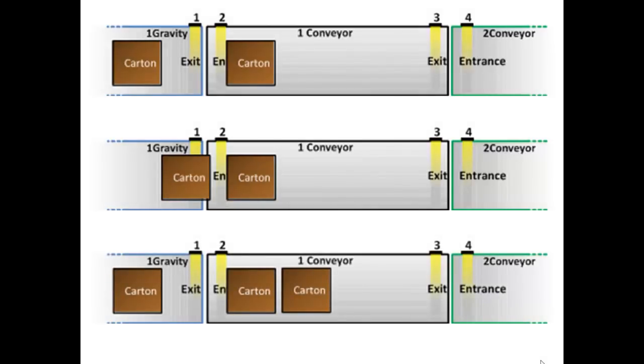And the logic then says, well, there's only one carton on one conveyor. It'll hold 4. It starts up one conveyor, and it pulls that carton that was resting against its leading edge through photo I2. In other words, it turns on until the carton breaks photo I2 and then continues to run to the trailing edge of that second carton. And then it stops.